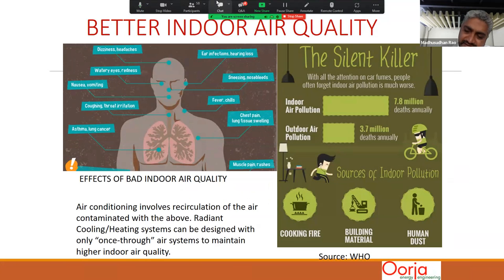One is you can design the spaces for better indoor air quality. There are many projects that we have done, others have done in the country, where air recirculation can be completely avoided when you are doing buildings with radiant cooling. The reason is, primarily the sensible cooling can be completely handled by radiant cooling, if your building envelope is good. And just a rule of thumb, if your building total heat load is somewhere around 300 to 350 square feet per ton, then you could look at radiant cooling handling the complete sensible load. But if you are at around 250 SFT per ton or so, then some amount of sensible load needs to be handled by the AHU. But let's talk about the situation where you have around 350 SFT per ton. Radiant cooling handles the entire sensible load.